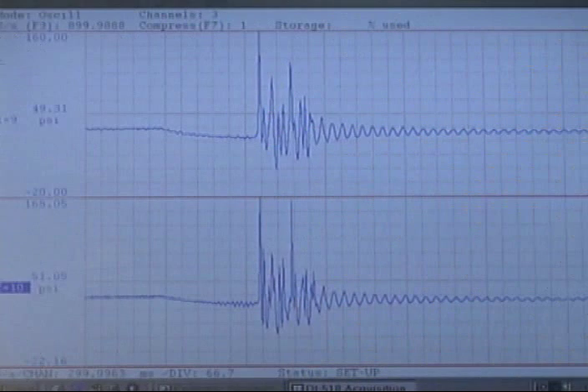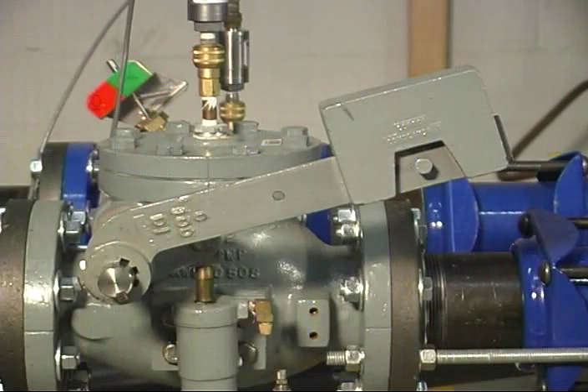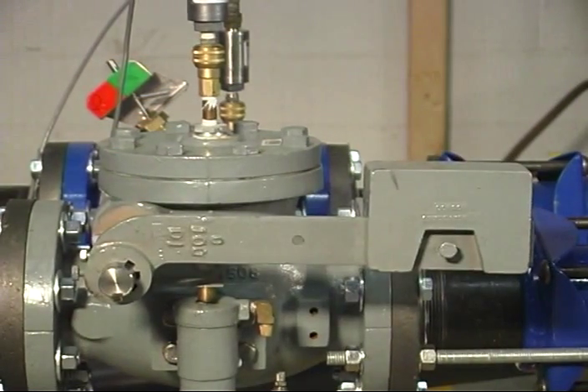And that was about 160 psi slam as recorded on the computer. You can see that the valve closed violently, causing the entire pipeline to shake.